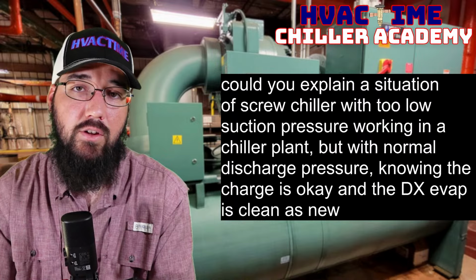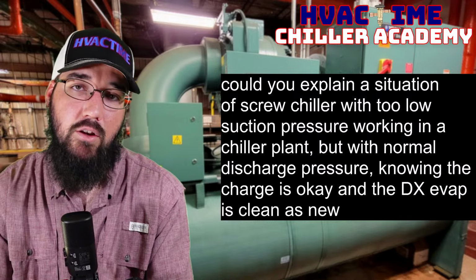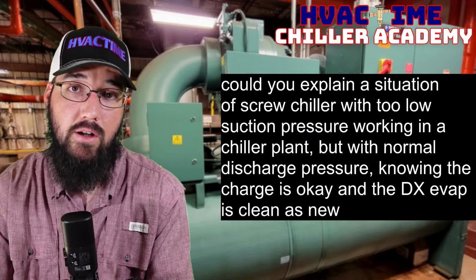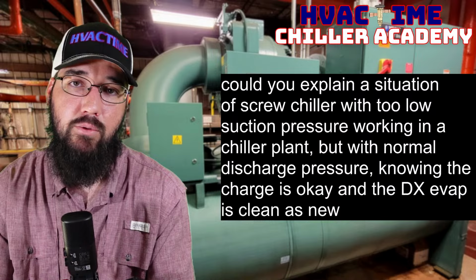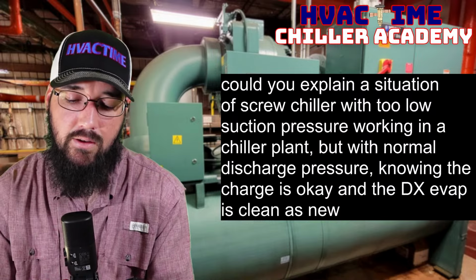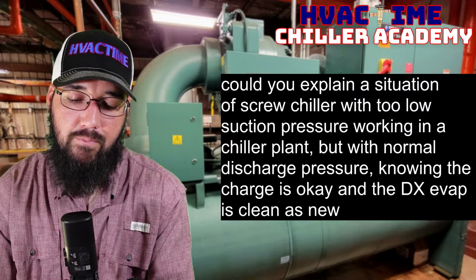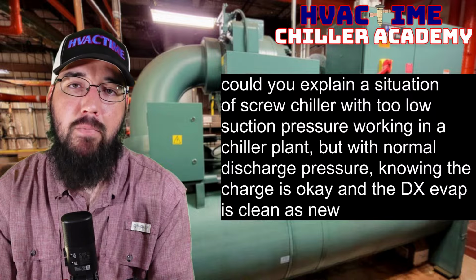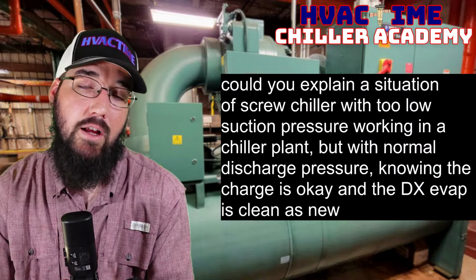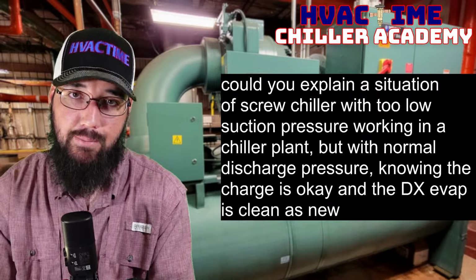So you may be suction limiting. You're at the low end of what that machine should be running at. Like you're right there at the trip point, but you're still taking in heat. It's not doing it very well, but it's happening.